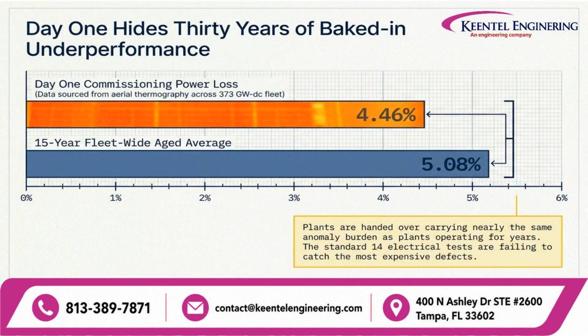Let's look at the numbers. Across aerial thermography data evaluating over 373 gigawatts of solar capacity, day one commissioning power loss averages 4.46%. Compare that to the 15-year aged fleet average of 5.08%. That means brand new utility-scale plants are being handed over carrying almost the exact same defect burden as assets that have been operating in the field for over a decade. The standard 14 electrical checklist tests are fundamentally failing to detect the most structurally expensive defects before substantial completion.